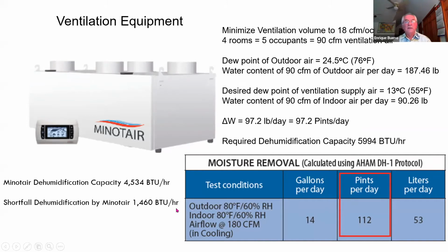Originally, we had designed the ventilation with Ventacity ERV coupled with Fujitsu DX coil for dehumidification, but the integration of the two became complicated, and also didn't provide enough dehumidification, forcing us to have an additional dehumidifier inside, plus another mini split, cooling only. So this shortfall will be remediated with a cooling only mini split that can take additional dehumidification and will be required anyway for sensible heat.